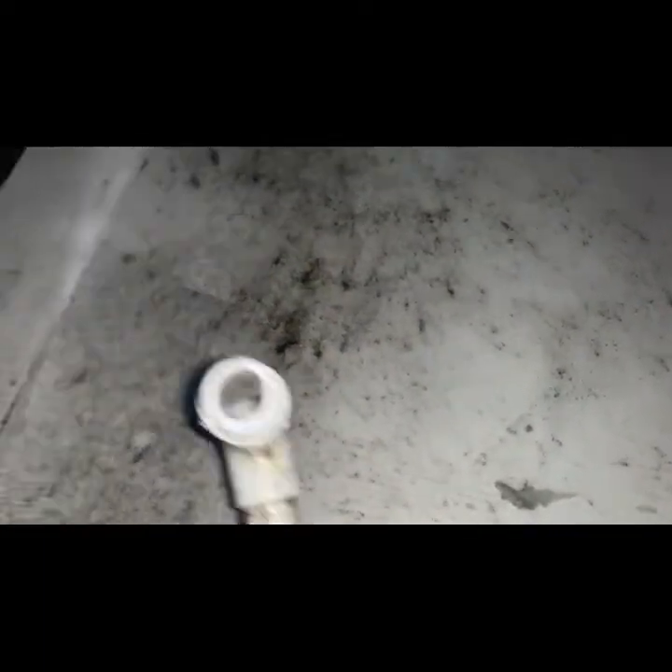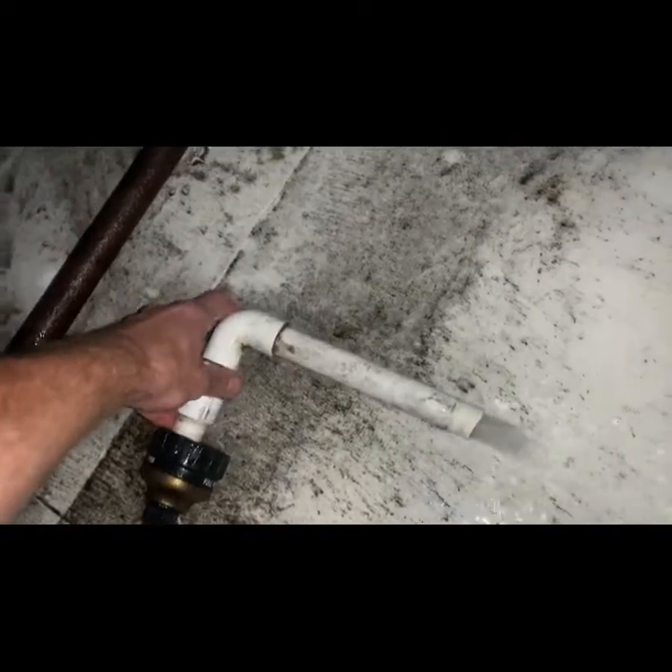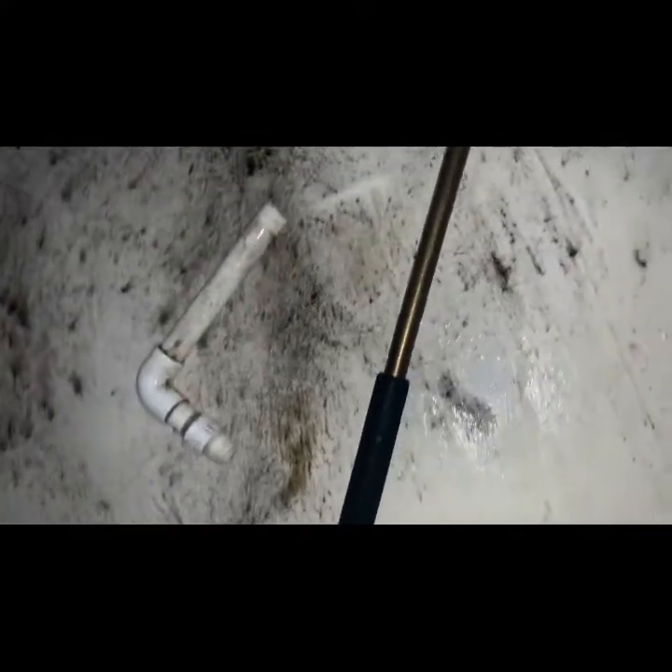He's got a water hose up here, so let's really clear this thing out. Somebody's been up here cleaning coils — not me. The owner does a lot of this stuff at this location himself. He's out of town, so his manager called me last night — otherwise he would have cleared it. The slugs go both directions. So it's not that it was clogged, it's that the trap came undone.